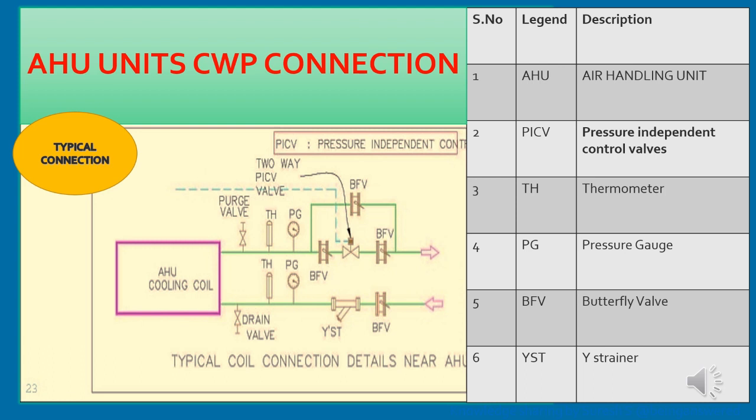Any dust particles or waste material will get collected in the strainer before reaching the coil, protecting the coil. Any sharp edges getting into the coil might damage it — that is the reason the strainer is used. Even though it is a closed circuit, as the chiller keeps running day by day, particles inside the pipe should not damage the coil. The accumulated dust material in the strainer will be removed periodically, and a butterfly valve will also be used.